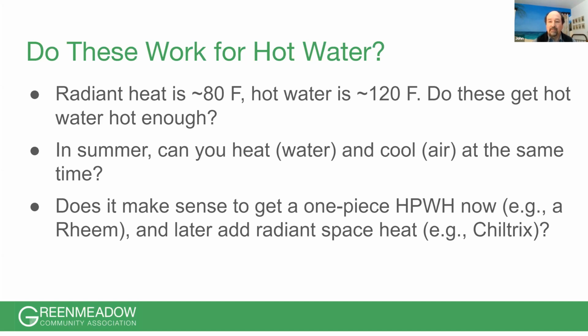Another thing that goes on with this type of system is that when it does go to domestic hot water heating and leaves hydronic heating, the buffer tank, which is maybe around 20 to 25 gallons, still has hot water in it. So while it has been diverted for several minutes, there's still heat, or air conditioning, left in the buffer tank to temporarily satisfy the space heating or cooling load. Because of the buffer tank, if it's radiant, we're not going to feel anything. But if it's fan coil, we might feel it, but maybe after 10 or 15 minutes.